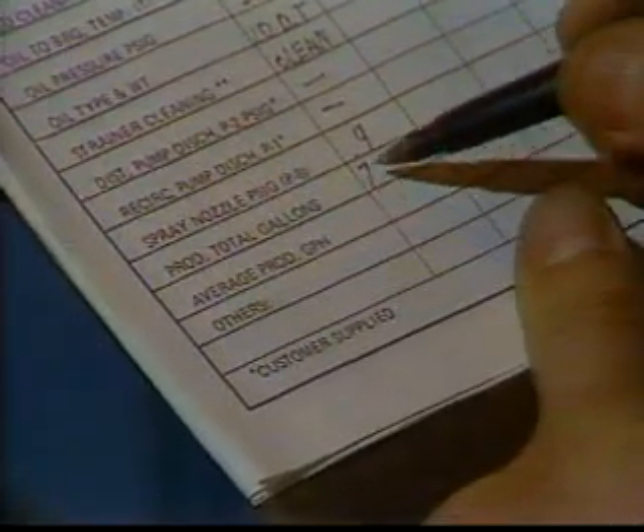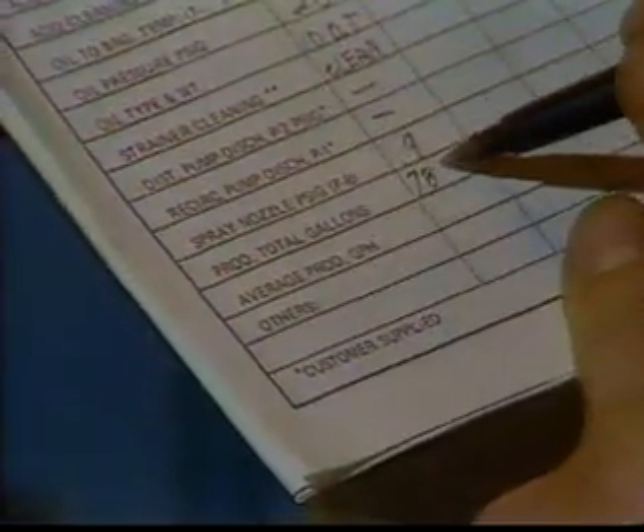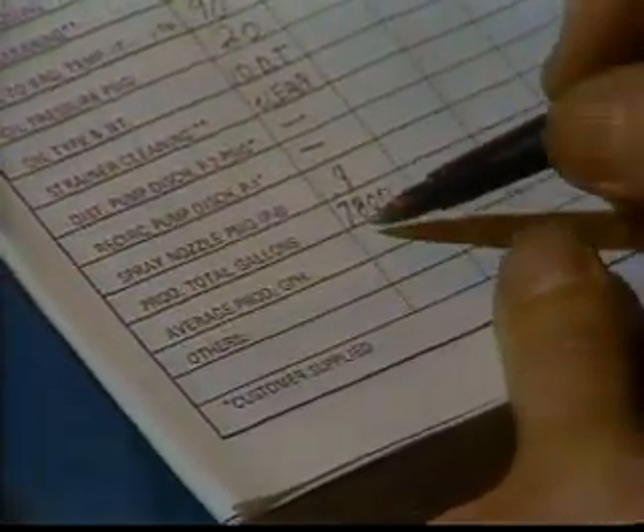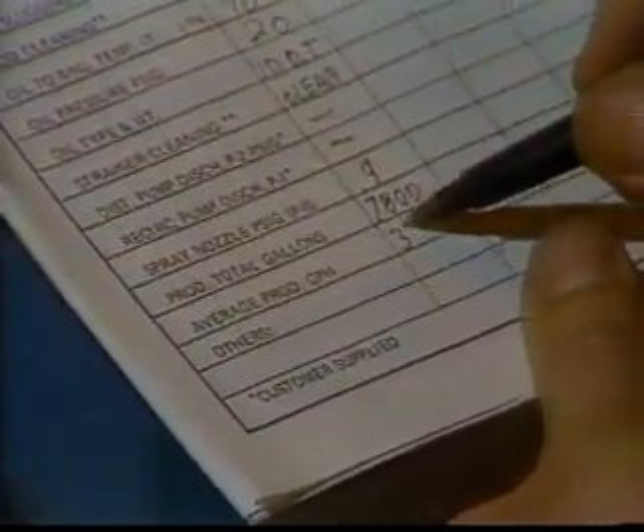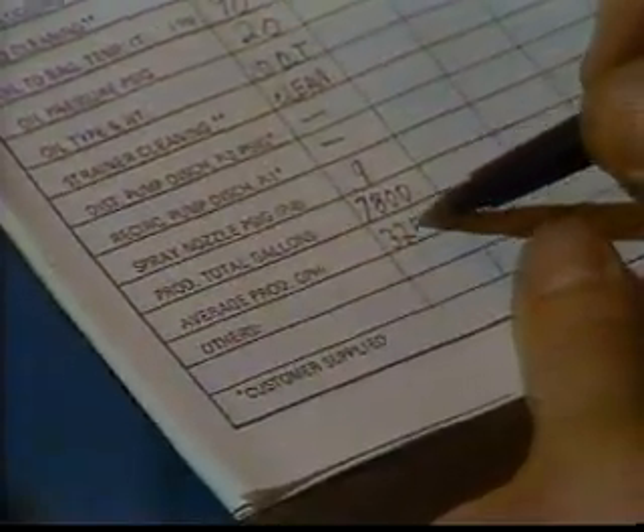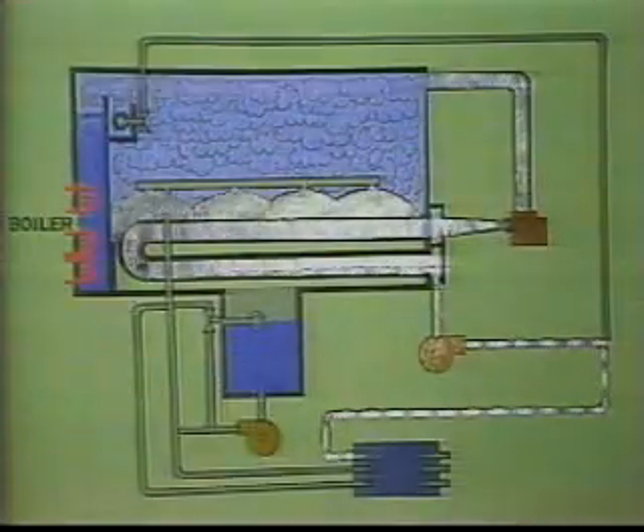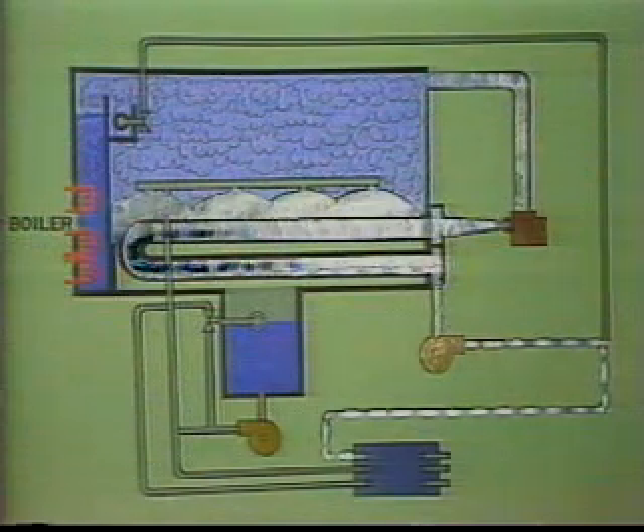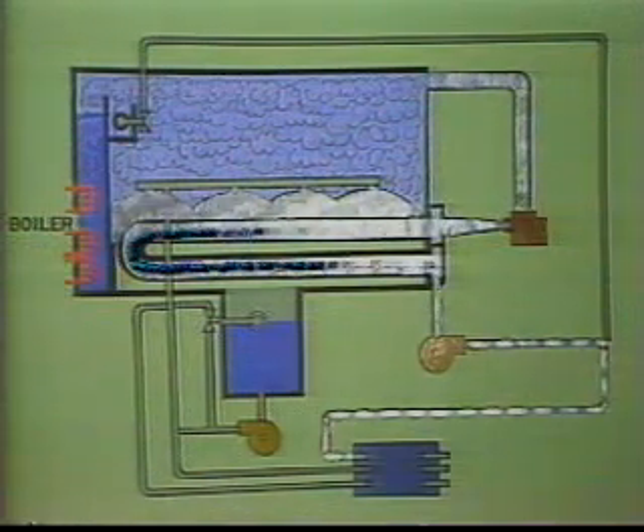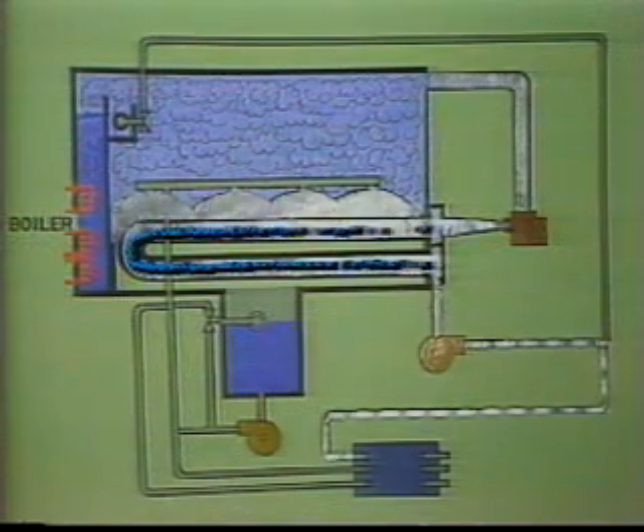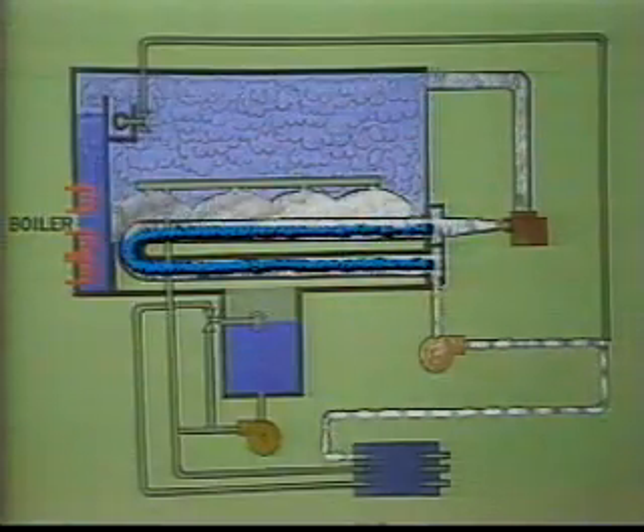And finally, production total in gallons and average gallons per hour. Be sure you know what these are supposed to be reading. As you already know, distillate flow will decrease as scale develops on the tube bundle. When distillate output drops to 80% of its rated capacity, the evaporator should be acid cleaned.